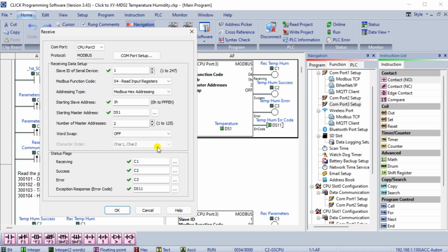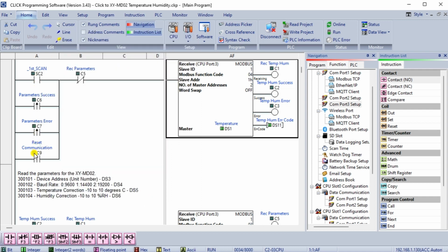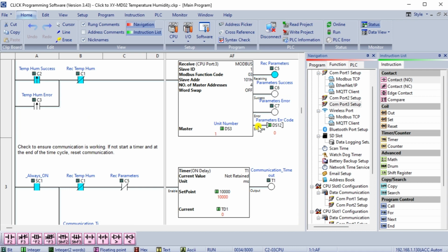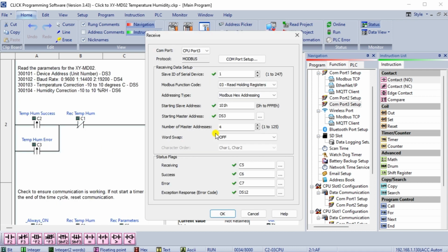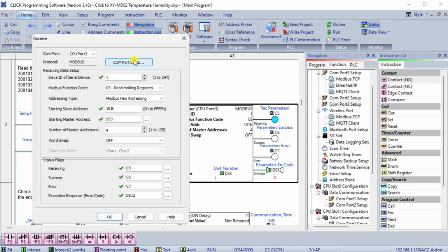The status flags are set for us to use in the ladder logic to control the communication timing and see any error codes encountered. Here is the completed rung 1 of the Click ladder logic code. The first scan is used to start the communication to the XY-MD02 sensor. The second Modbus instruction will receive data for the sensor parameters. Again, slave server unit 1 is used. We will use the 03 read holding registers function code at Modbus hexadecimal address 101 this time. We will read 4 addresses and place them in the click PLC memory starting at DS3. Status flags are then set up to use in our ladder logic.